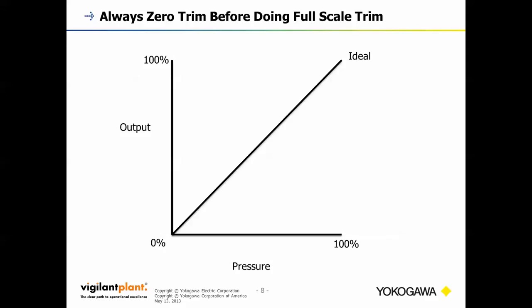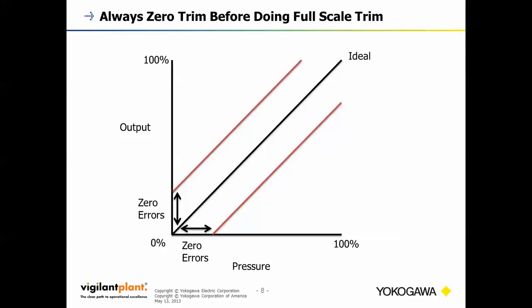So on the x-axis, we have our pressure reading, or our pressure generated, so the pressure that the pressure transmitter is measuring, and then we have the output of the transmitter. Ideally, it's a linear device. So at 0 pressure, it should read 0%, and at 100% pressure, it should read 100% output. But there can always be errors, so we're going to go over what those errors are and how 0 trimming and full-scale trimming can affect that.